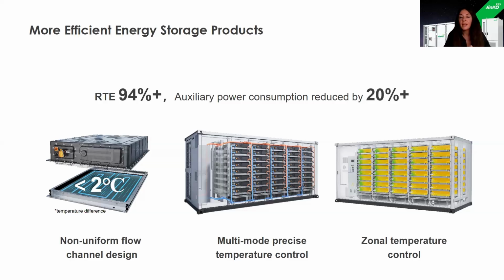Regarding the non-uniform channel design, from a thermal management point of view, this ensures more precise and balanced cooling temperature across zones inside the battery module. We can precisely control the temperature and reduce thermal gradients between the cells, keeping all cells at the same temperature level and reducing degradation rates, boosting safety and performance of the battery.